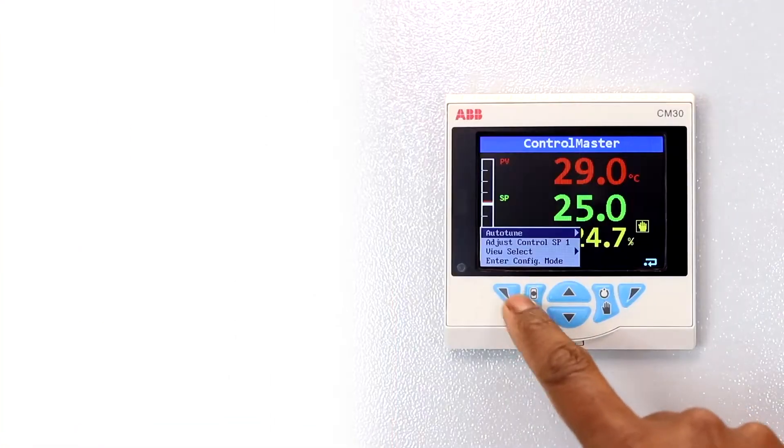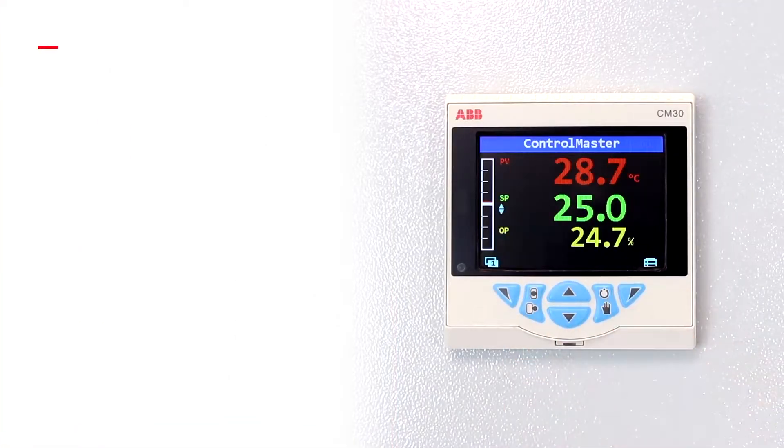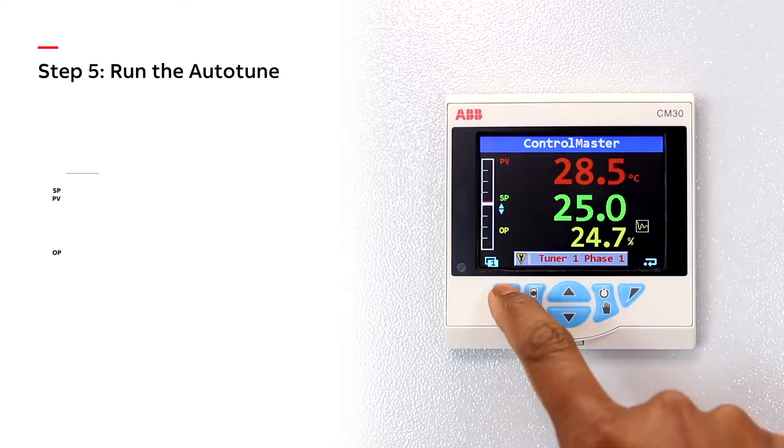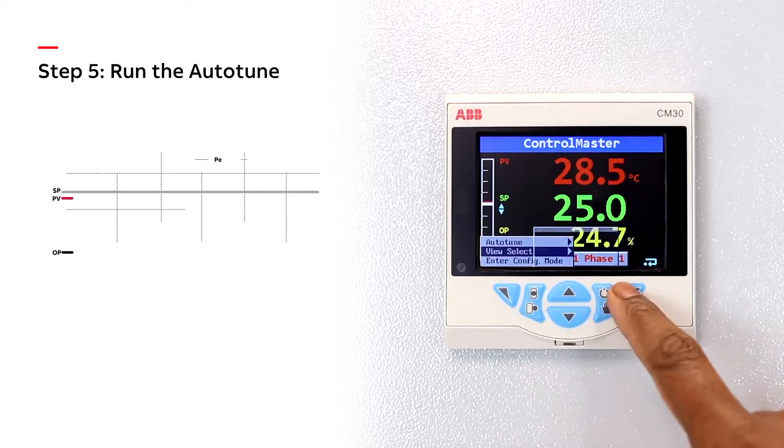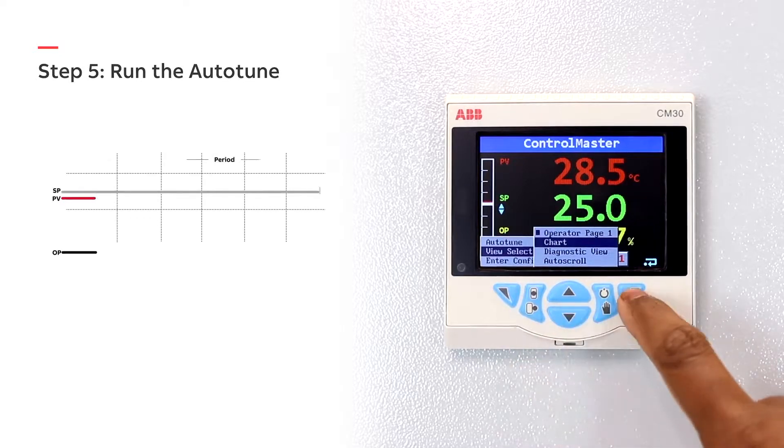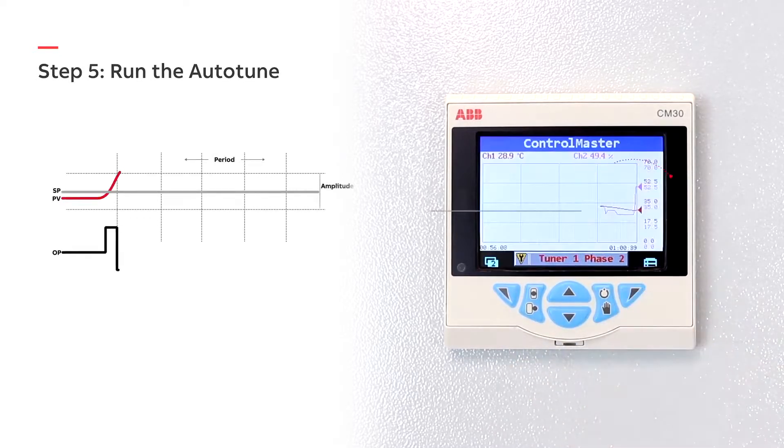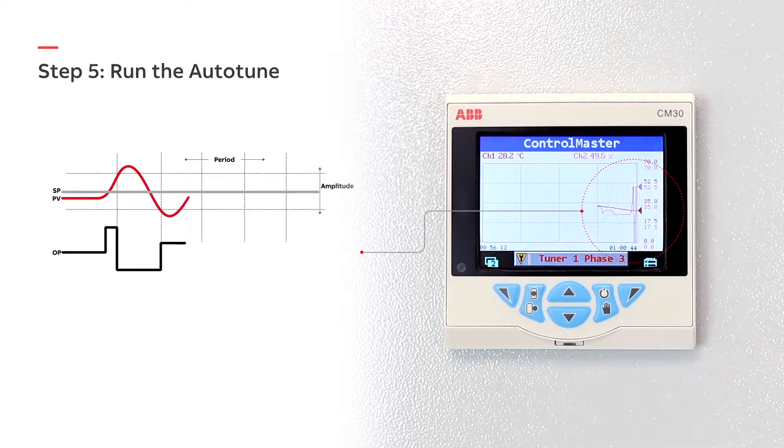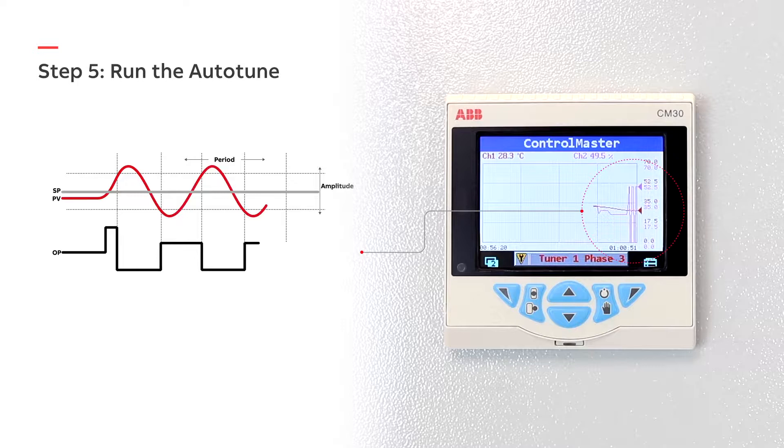Step 5: Run the Auto-Tune. Auto-Tune steps up and down the controller's output to create a controlled oscillation of the process. Based on this oscillation, optimum PID values are automatically calculated.